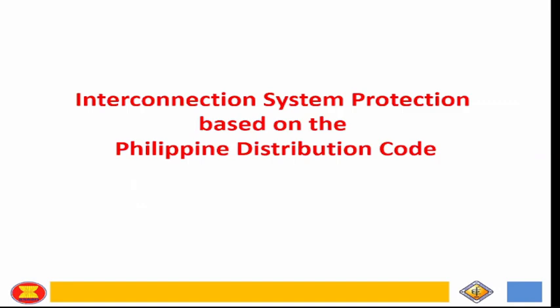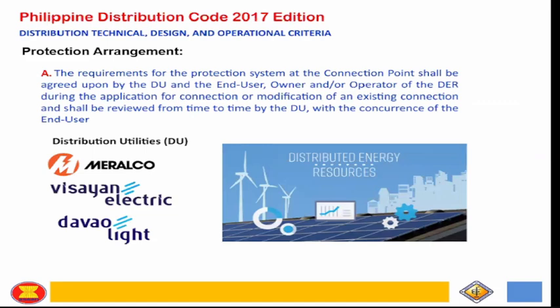So based on the Philippine Distribution Code, mayroong provision dito. The requirement of protection system at connection shall be agreed upon by the DU and the end user. So hindi pwedeng si DU lang ang magsabi na ito talaga yung requirement namin. Kailangan dito kasi mayroon yung impact, if yung end user, yung DG owner, kailangan mayroon ding counterpart na engineer na knowledgeable, na baka over din yung requirement. Kung wala namang abogado for the DG part, kasi somehow cost din siya, kailangan mag-agree. It's actually a mutual agreement between the DU and the DG owner. Okay? So yun yung rule of thumb dyan.